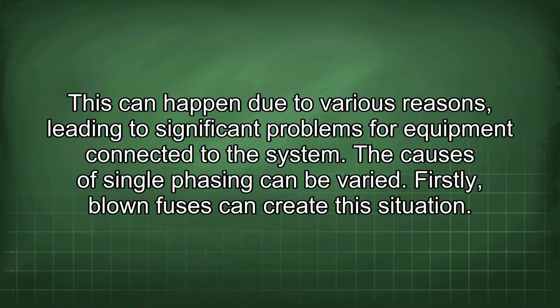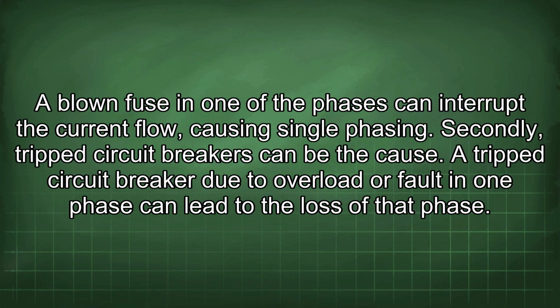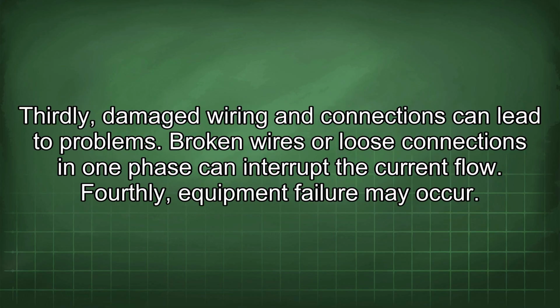This can happen due to various reasons, leading to significant problems for equipment connected to the system. The causes of single phasing can be varied. Firstly, blown fuses can create the situation. A blown fuse in one of the phases can interrupt the current flow, causing single phasing. Secondly, tripped circuit breakers can be the cause. A tripped circuit breaker due to overload or fault in one phase can lead to the loss of that phase. Thirdly, damaged wiring and connections can lead to problems. Broken wires or loose connections in one phase can interrupt the current flow.